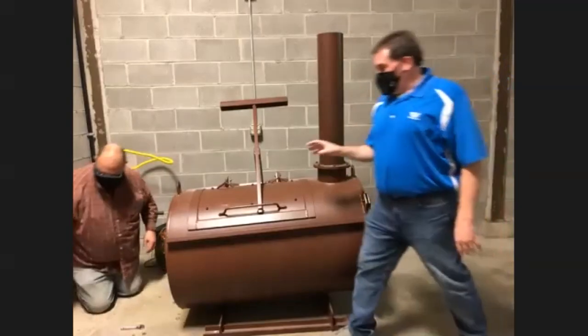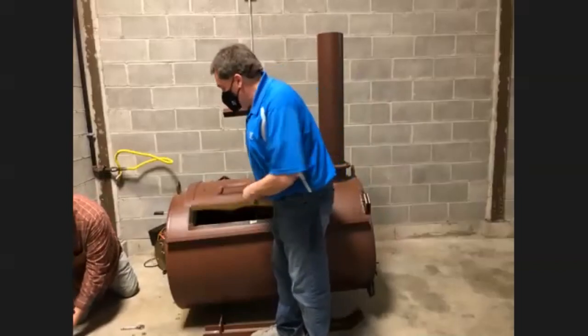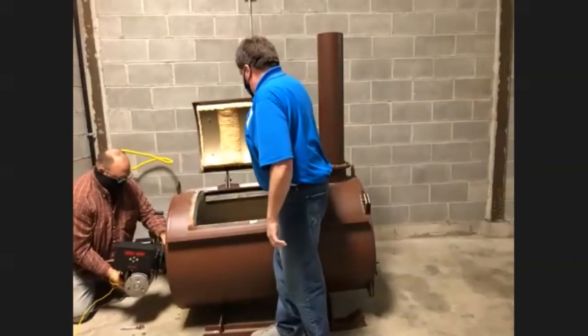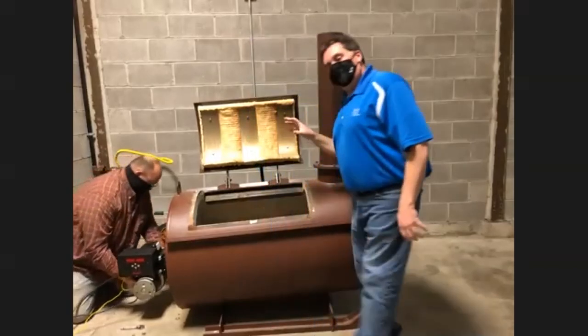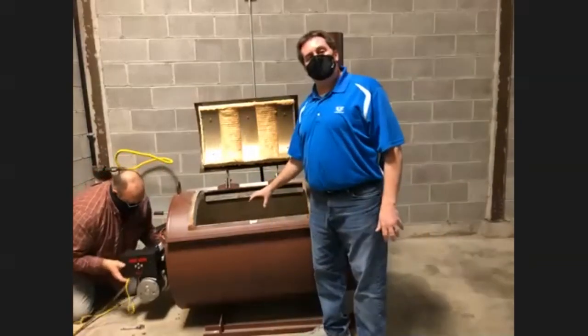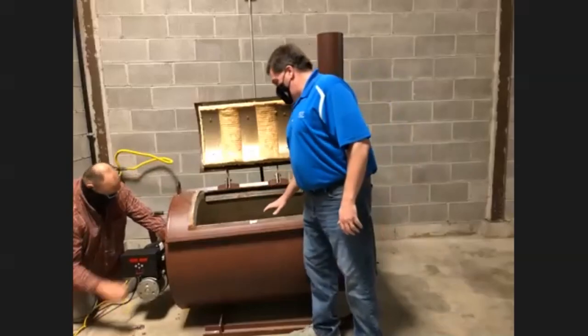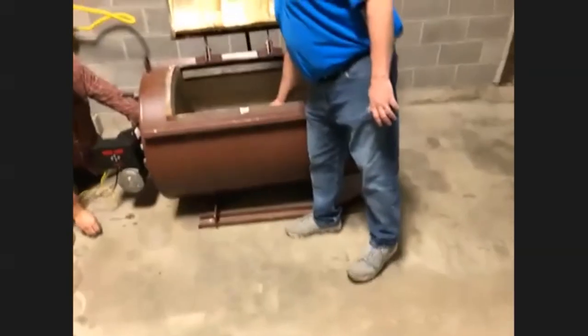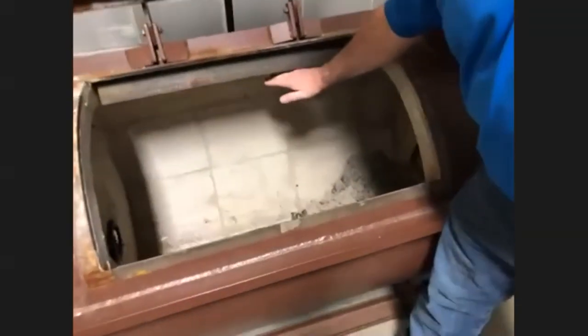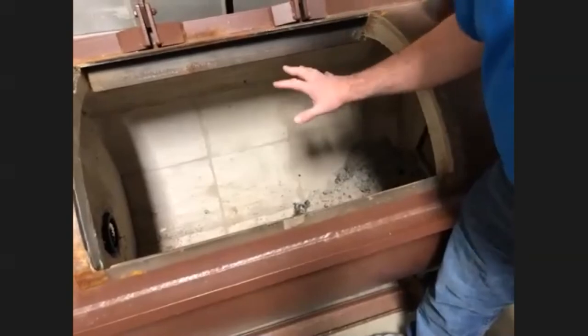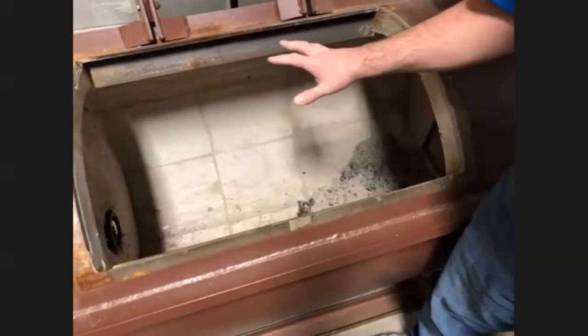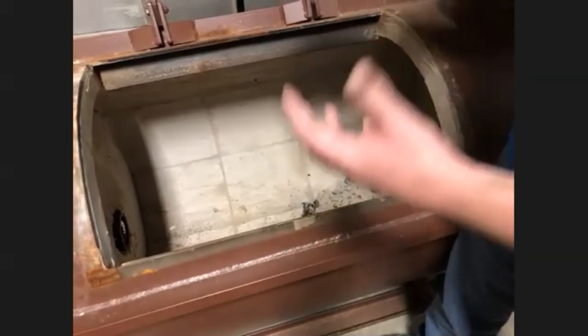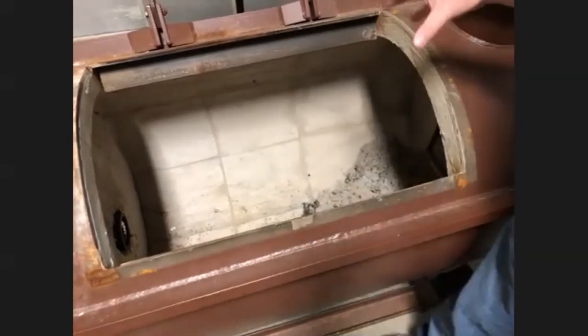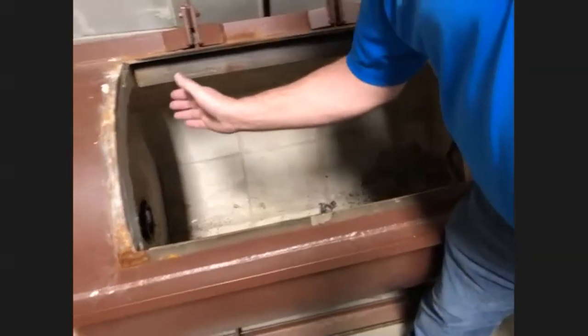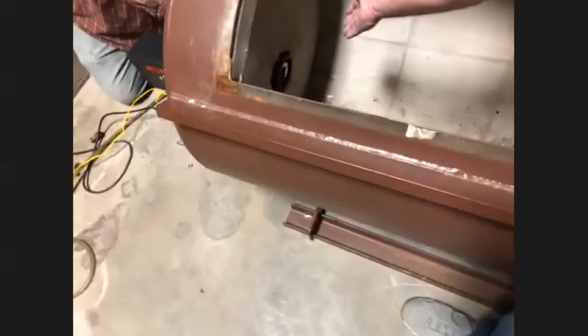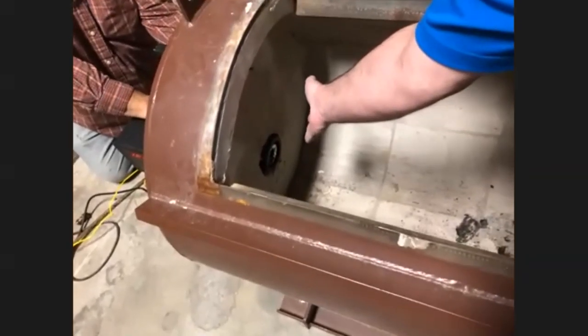And when we start talking about units and when I discuss the sizes of them, we built up this model here. When you start to load these units, they're set up where you put your capacity up, and you load them roughly 3/4 full. Typically, that's about where these angle irons are. You always want an open gap up here. That allows a good air mixture with your fuel mixture and flames so things circulate properly and burn efficiently. Also, when you do load these, you do not want any media, anything within 12 inches of the burner itself.